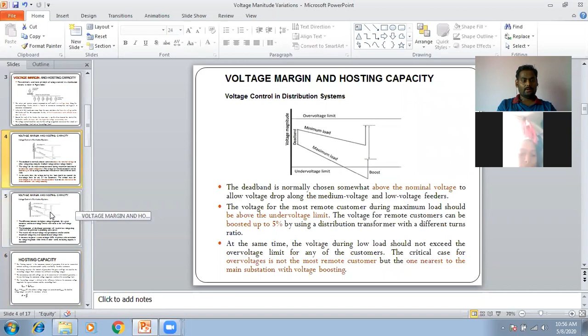And the hosting capacity is the amount of generation that gives a voltage rise equal to the over voltage margin, right? So whenever we talk about hosting capacity, that gives the voltage rise equal to the over voltage margin. You can see this is the over voltage margin, right? But it should not go beyond the over voltage limit, right? After that, the maximum permissible voltage rise with the connection of distributed generation is the one that brings the maximum voltage magnitude exactly to the over voltage limit, right?